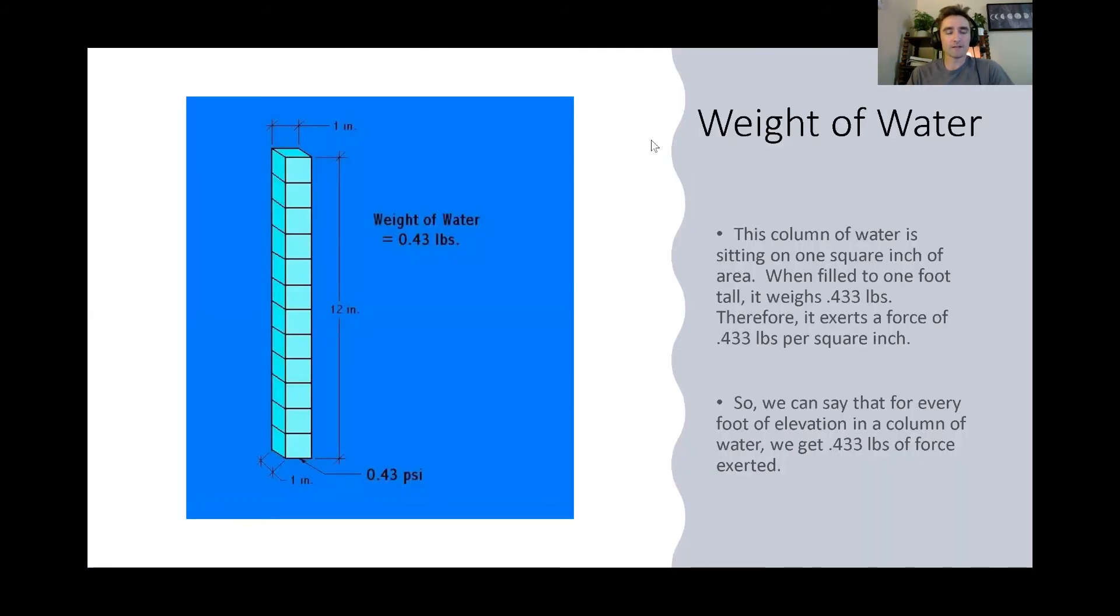Here's a graphic that is representing the concept of psi. So imagine each of these cubes is one cubic inch. You stack them on top of each other so there are 12. So it's one foot tall, 12 inches tall, and the bottom is one square inch. What you end up with at the bottom is a weight. Like if that could be on a scale, it would be 0.43 pounds. And that is how we define water pressure. So for every foot of elevation in a column of water, we get 0.433 pounds of force exerted per square inch.